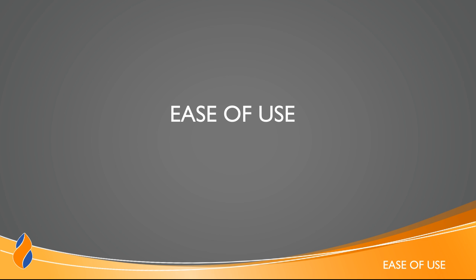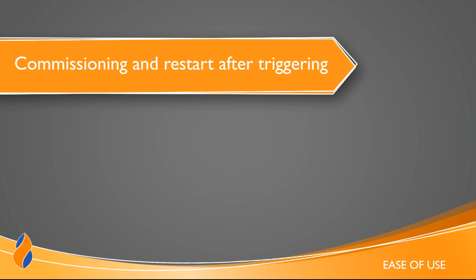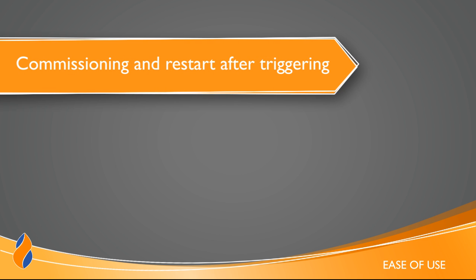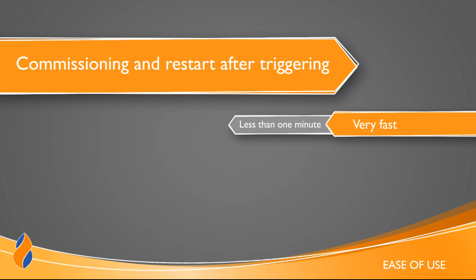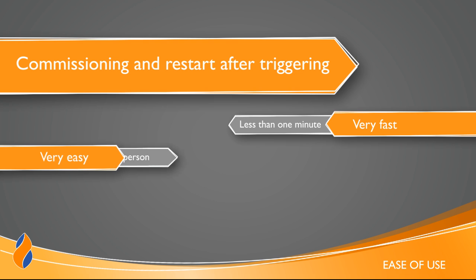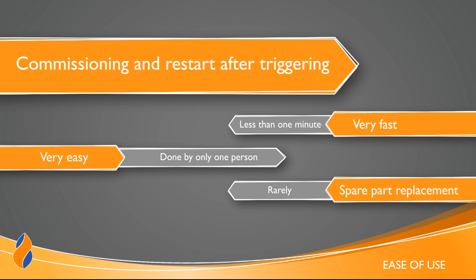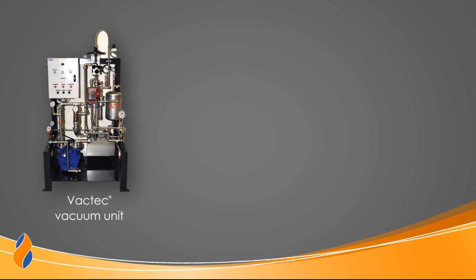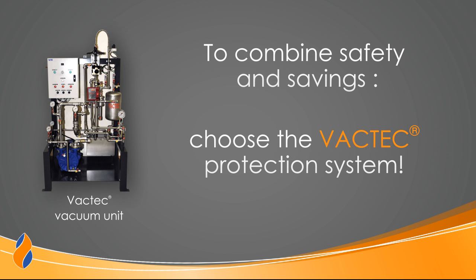The VACTEC system is also characterized by its simple commissioning and restart after triggering. This commissioning is very fast, as it requires usually less than 1 minute. It is very simple because it can be done by only one person. The spare parts replacement is rare, easy and quick. To combine safety and savings, choose the VACTEC protection system.